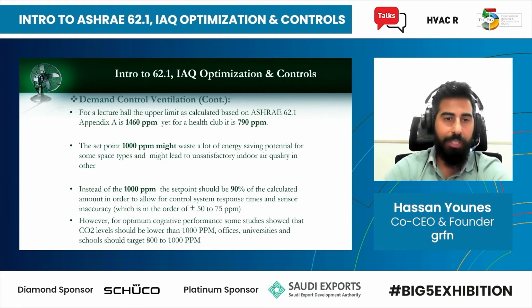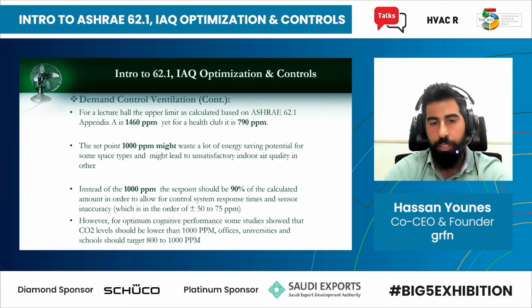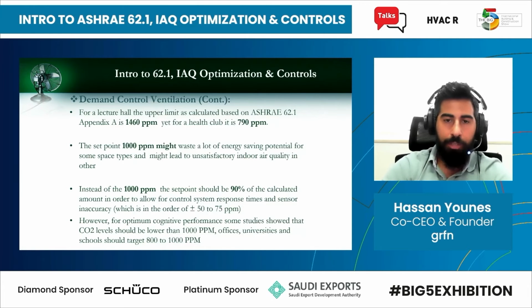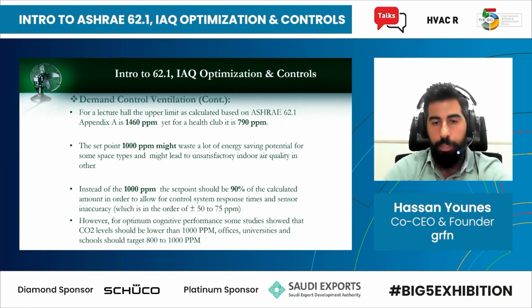You should not panic from that. That's completely normal. The 1,000 is mainly for office buildings with an occupancy of 1 person per 20 square meters. So in general, what we recommend is to look at the steady state concentration levels, and then use 90% of that calculated amount as a set point rather than just using 1,000. Mind you that for offices, it is recommended to go even below 1,000 because some studies have shown that cognitive abilities are better with a low CO2 level. So it depends on the occupancy type. I would suggest for schools, universities, and offices, go to the lowest possible. Maybe 800 ppm would be the recommended value.